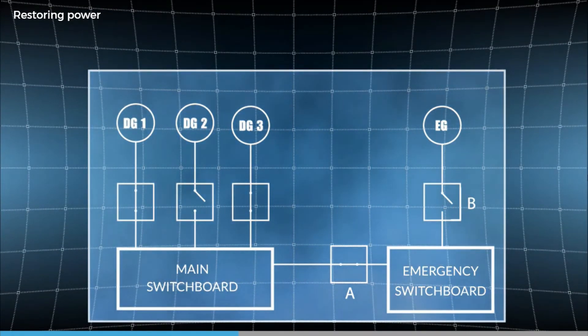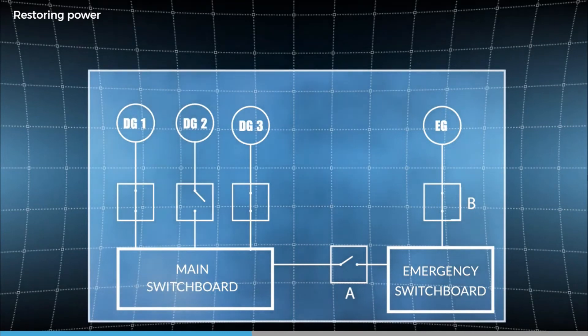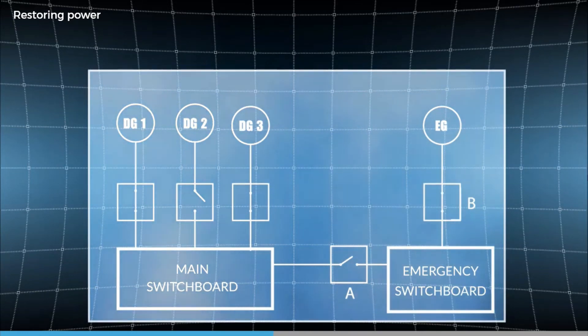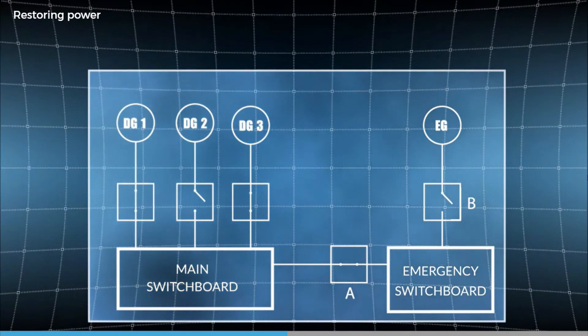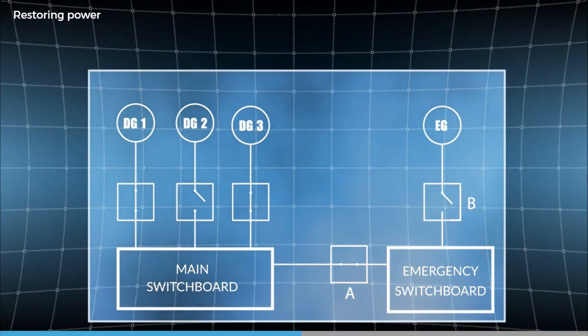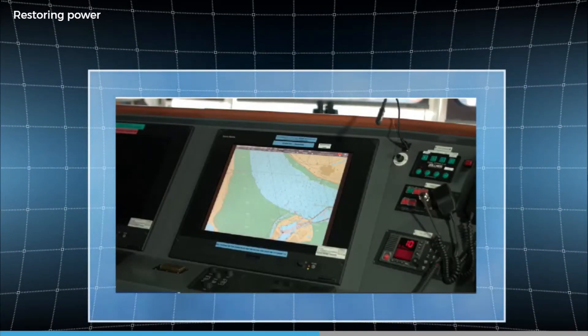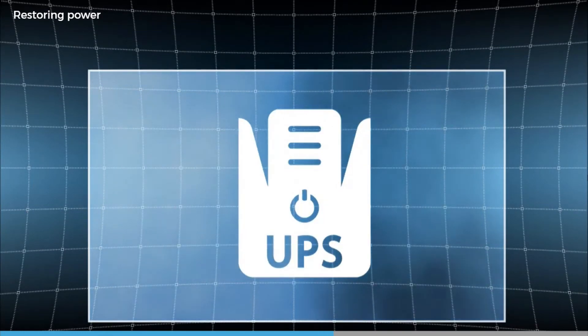If we can synchronise them, great. If we can't, then keep in mind that there might be a momentary loss of supplies to anything fed from the emergency switchboard. So know what this affects since it could potentially cause another blackout. For instance, if it is supplying power to the main generator fuel pump.